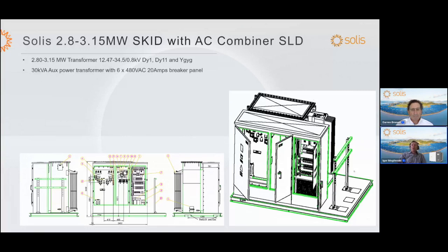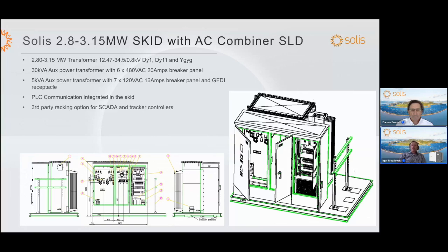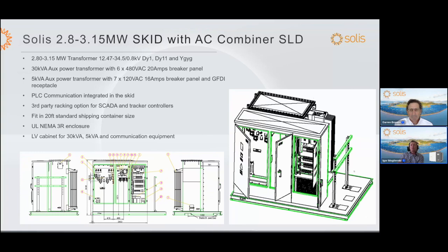The auxiliary power equipment is the same: 30 kVA transformer, 5 kVA auxiliary transformer, PLC communication integrated in the skid, and third-party SCADA racking. You can see all the circuit breakers located in the low voltage cabinet, including the transformer. It fits in a 20-foot container. 3 of them could fit in a 40-foot container, so you really could save a lot of costs on shipping. And UL NEMA 3R enclosure. The low voltage cabinet has the 30 kVA, 5 kVA, and communication equipment.